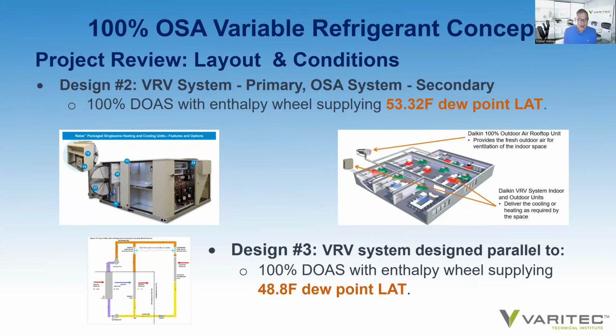Design number three, however, we decided to take it a little further. We looked at a variable refrigerant system with a 100% outside air unit that supplied lower dew point supply air. Why would we do that? And what advantage does that have to offer? Well, let's look at the findings.